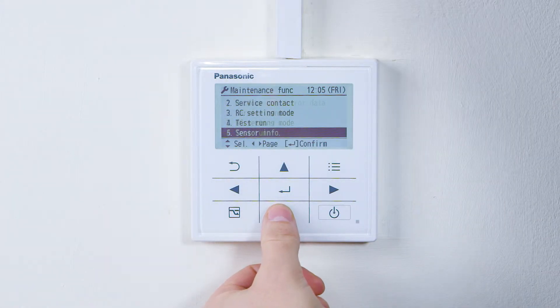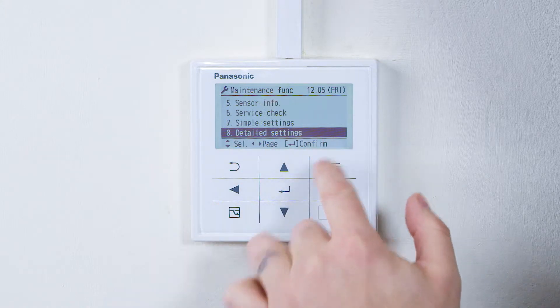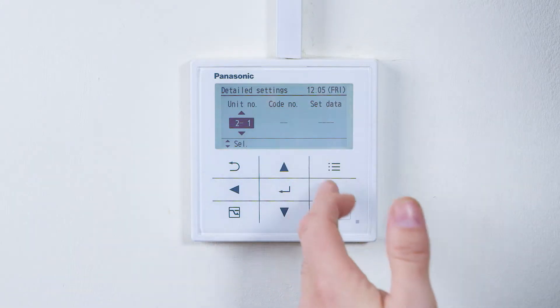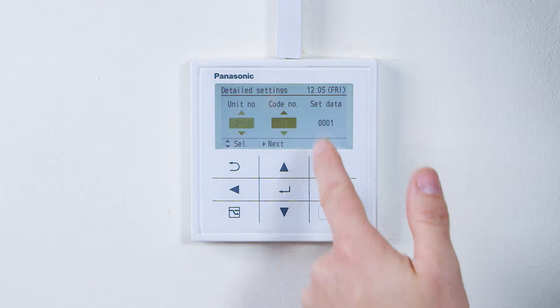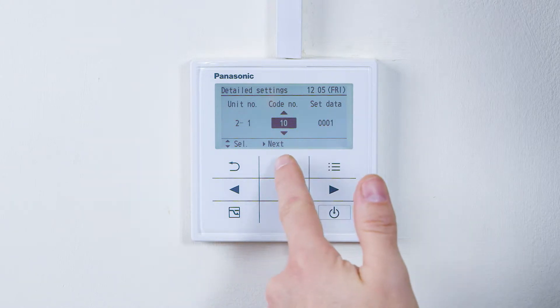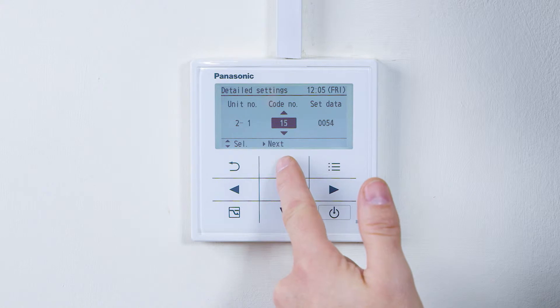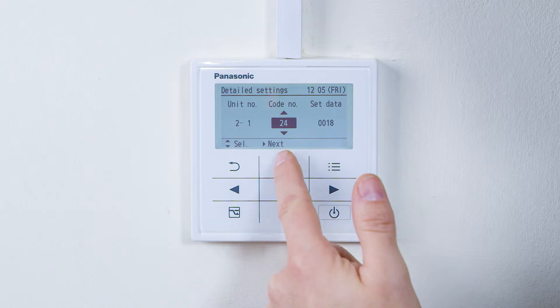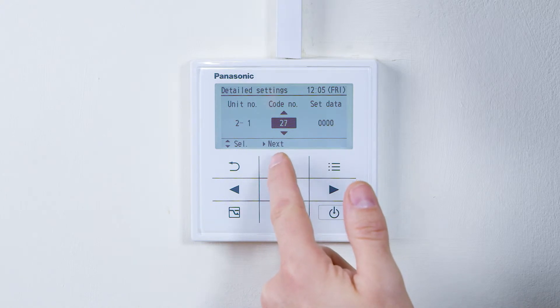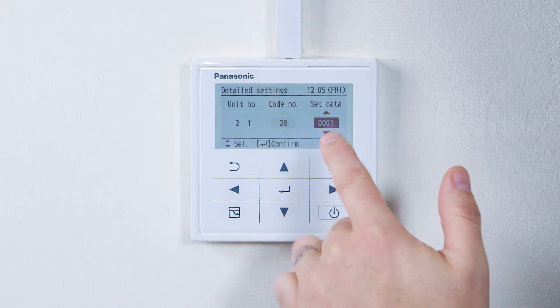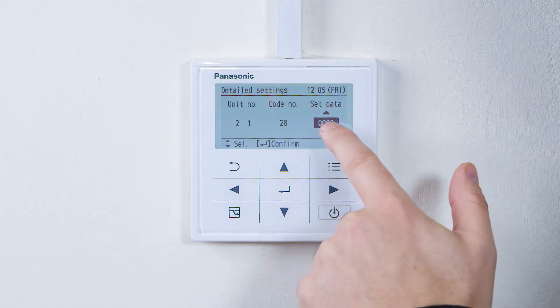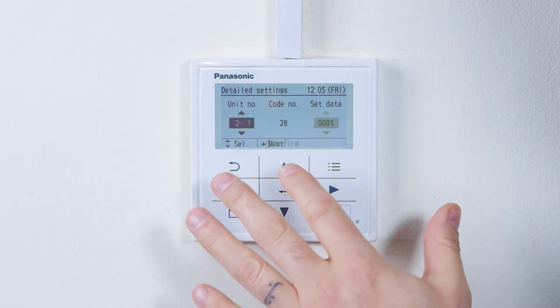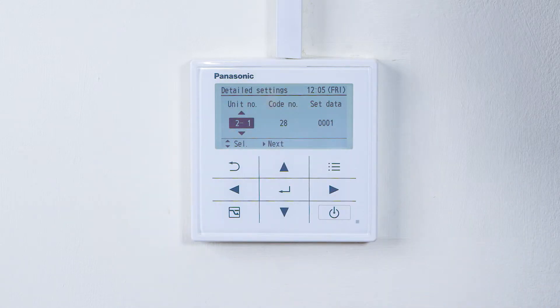Once in, scroll down to number 8 — detailed settings — and press enter. A unit number will be displayed on the left hand side. The code number will come up as number 10; it will always start on code number 10. At that point we can change the code numbers — for example, we can go all the way up to code 28. On the right hand side is where you set the data: if it's 0000 it's not set; if it's 0001 then it is set. Press enter and now you've set auto restart after power failure.